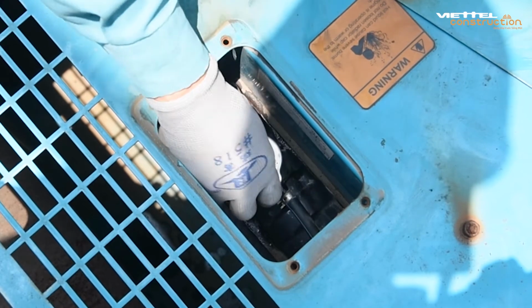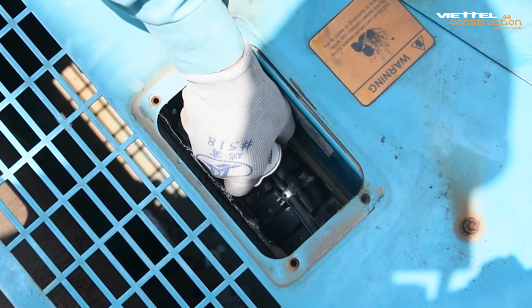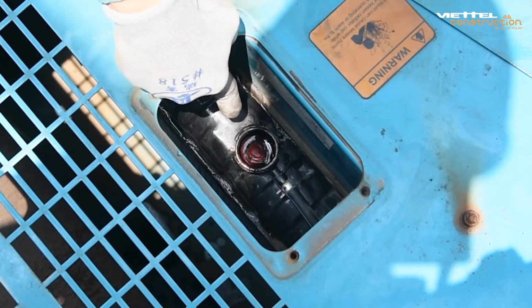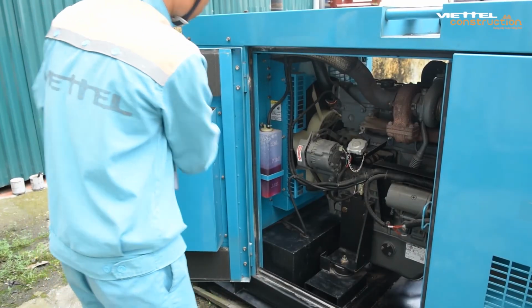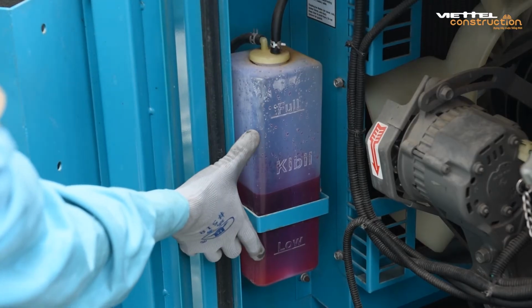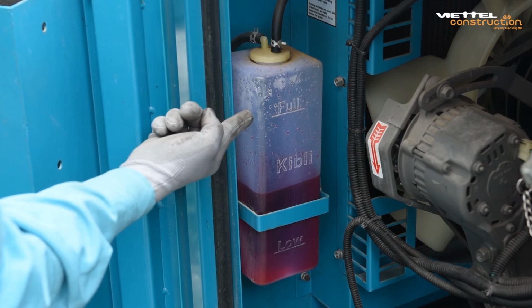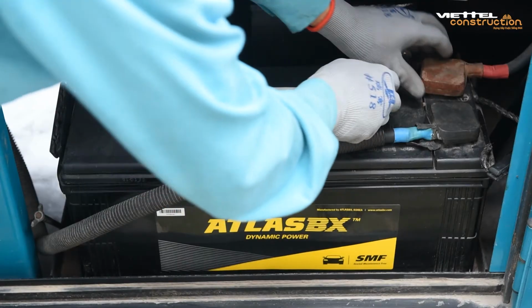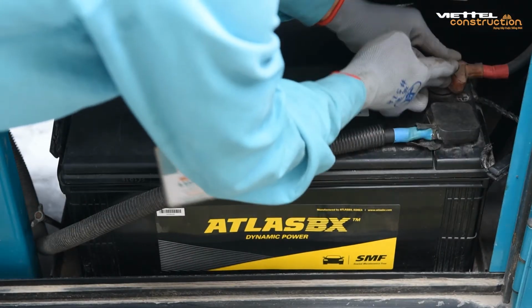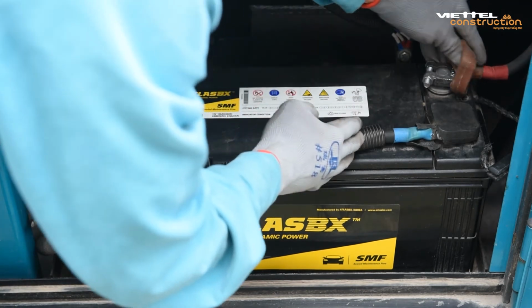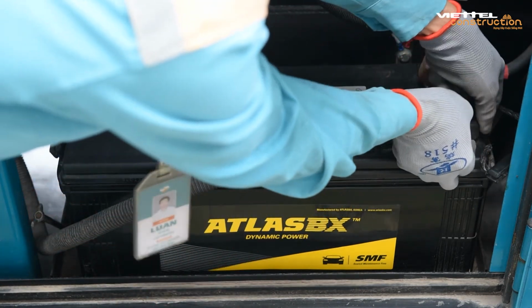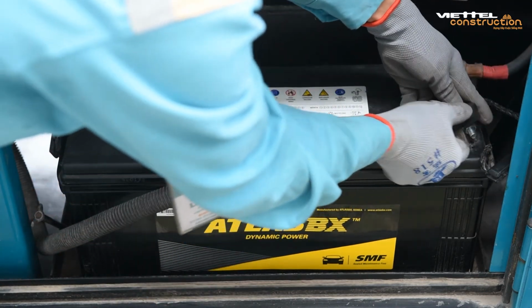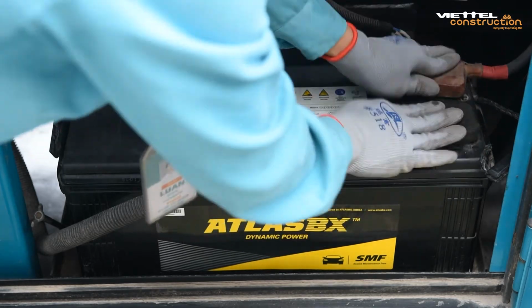Use a screwdriver to open the lid. Make sure the cooling water level is full to the neck of the radiator. The water level is between the upper and lower limit line. Check the startup battery. The battery must be connected to the right polarity. Positive of battery to terminal positive of starting motor. Negative of battery with terminal negative of the starting motor.